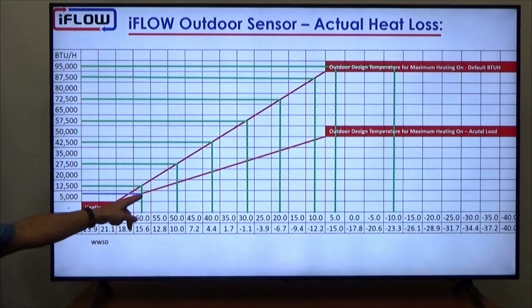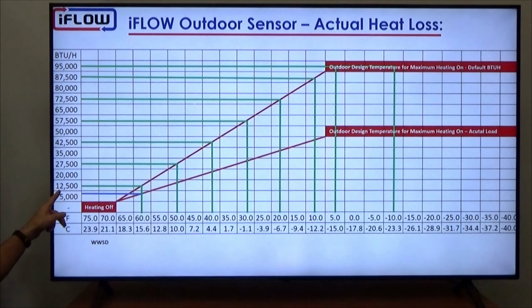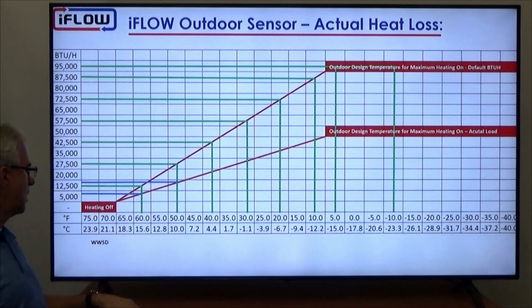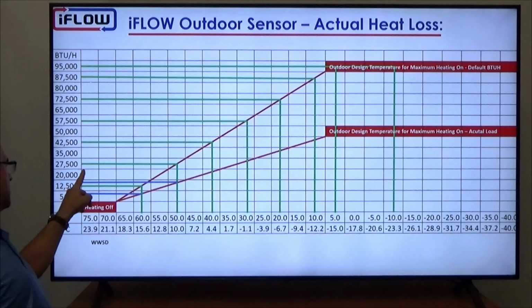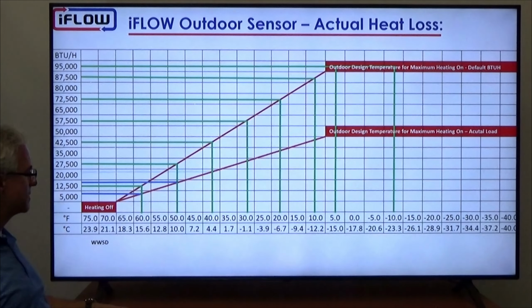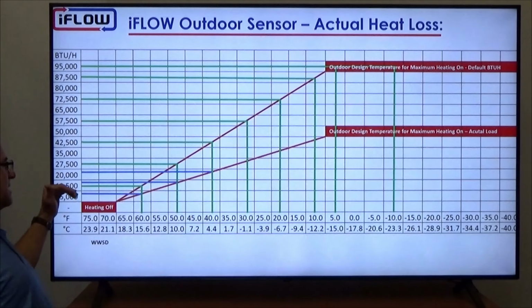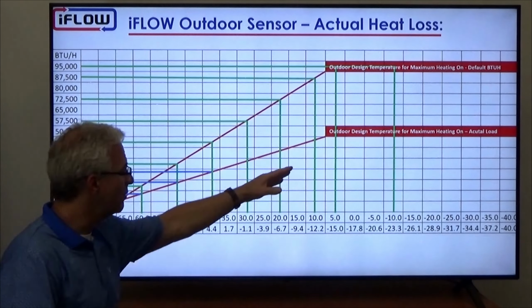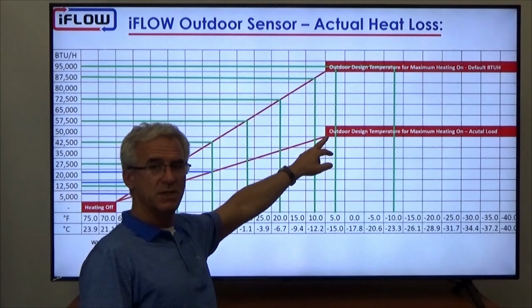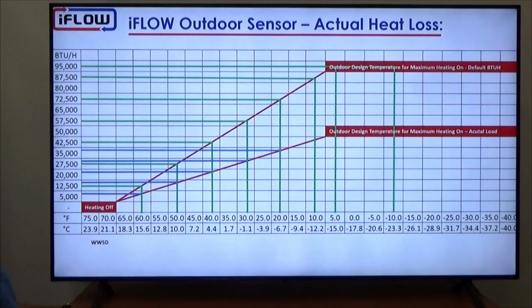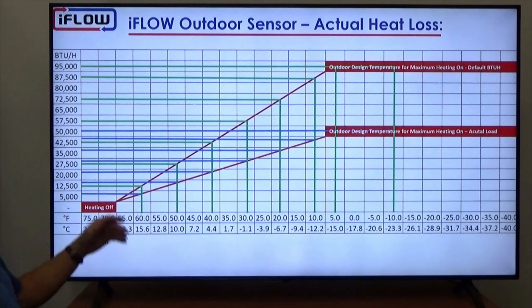So for example, if it's 60, instead of delivering 12,500, which we did initially, now we're delivering just over 5,000. So maybe 6,000, it'll be a little bit more than half of what we have up here. And the same for 50. At 50, instead of delivering 27,500, we're delivering 14,000 or 15,000. So for each temperature, we're delivering less and less BTUs because we don't need as many. Instead of 95, we're only at 50,000 BTU load on the house. So it makes sense that we deliver a correspondingly lower amount of BTUs because of the smaller heat load of the house. So this is what the outdoor sensor does.